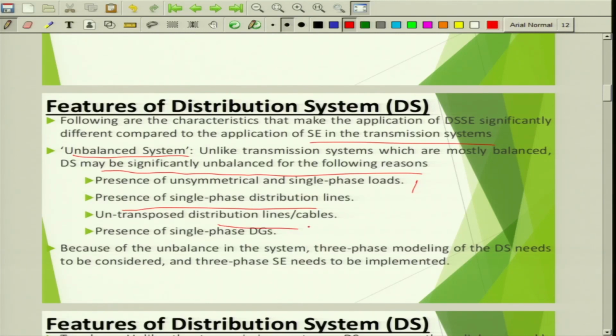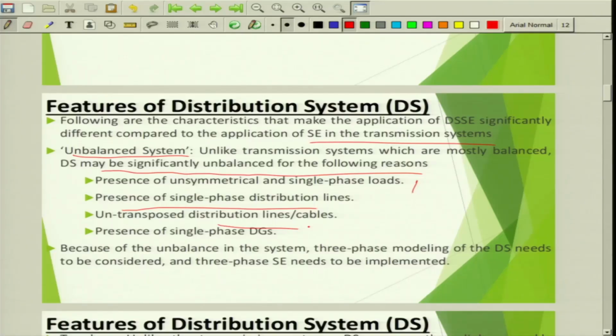In transmission system, the transmission lines are transposed, after some distance the A phase may be shifted to the location of B phase, and B phase line could be shifted to the position of C phase, vice versa. So, they would face a balanced load actually at the transmission level, whereas in the distribution system it is not transposed. So, there is a very high chance that the load may be unbalanced in the distribution system side, and presence of single phase distribution generations, or diesel generators also there could be. So, these are some of the challenges.